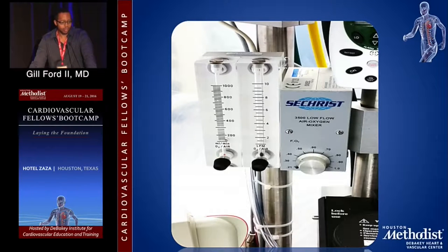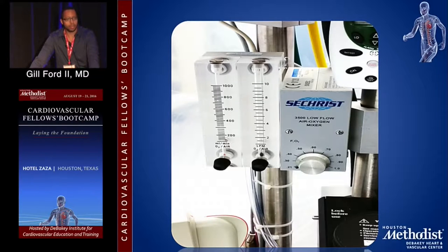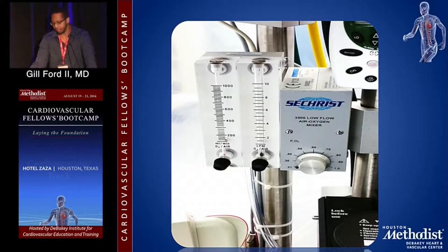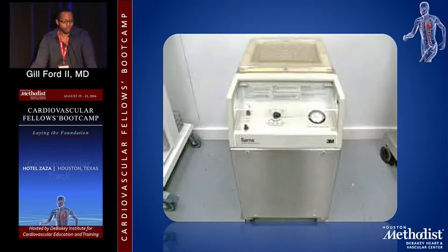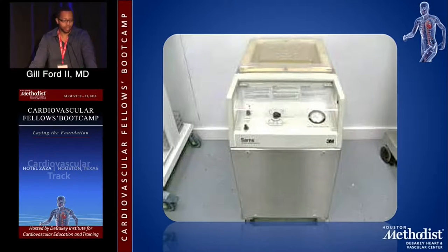This is how we deliver gas. The silver part is the blender, which allows us to dial in what percent of oxygen we want to deliver to the patient. The clear side is the flow meter, which dials in how much oxygen we want to deliver in liters. We also have an external heater-cooler that hooks up to the heat exchanger — you'll see various models at different institutions; this one is the Sarns 3M.